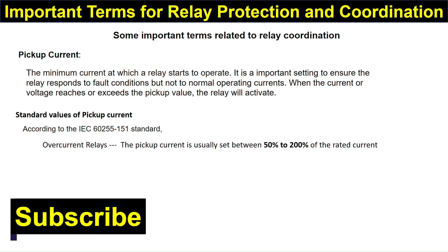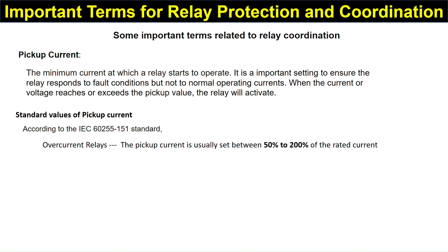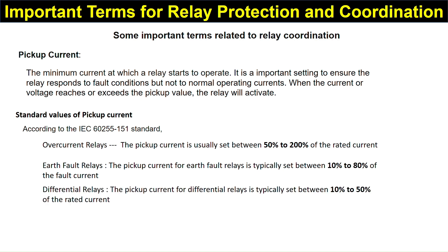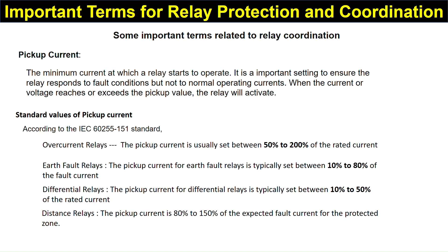Standard values of pickup current according to IEC 60255-151: for overcurrent relay, pickup current is usually set between 50% to 200% of rated current. For earth fault relay, it is typically set between 10% to 80% of fault current. For differential relay, it is typically set between 10% to 50% of rated current. For distance relay, it is 80% to 150% of the expected fault current for the protected zone.